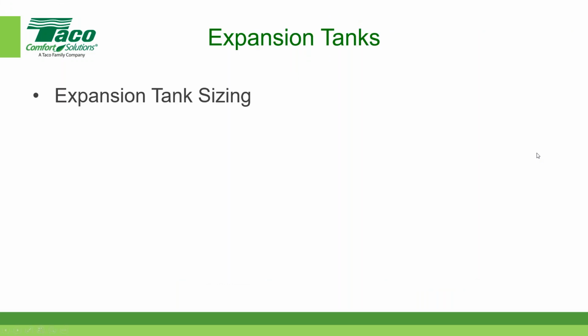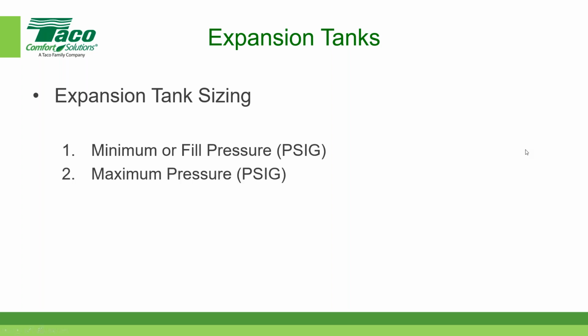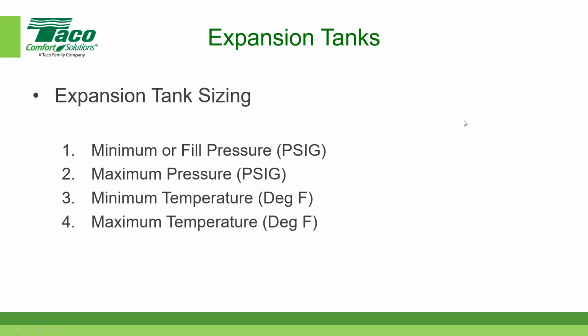So what is my next slide here? Expansion tank sizing. When it comes to an expansion tank, we need to know things like the minimum or fill pressure, which in our example before was the pressure at the beginning when the tank was empty. We need to know the maximum pressure, and we'll show you how to figure out the minimum and maximum pressure in a system. We also need to know the minimum temperature for the fluid in our system, the maximum temperature, and the fluid type. That's very important.